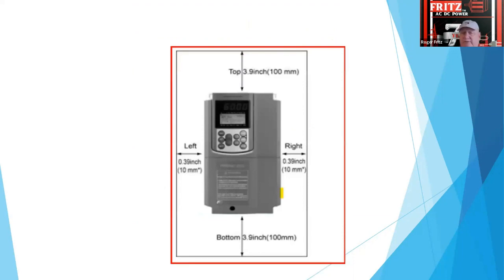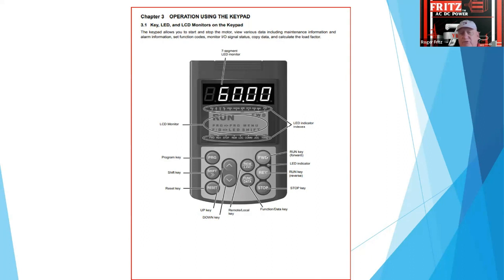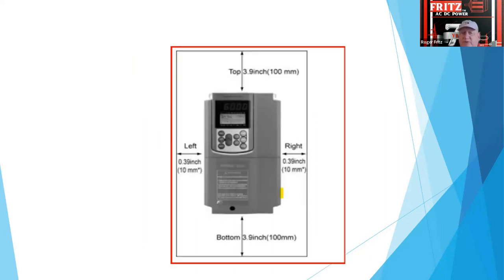The other thing you need to be aware of when you install the controllers, if it's inside of an enclosed environment, is that you have air room around it, and also do a thermal capacity of that room.